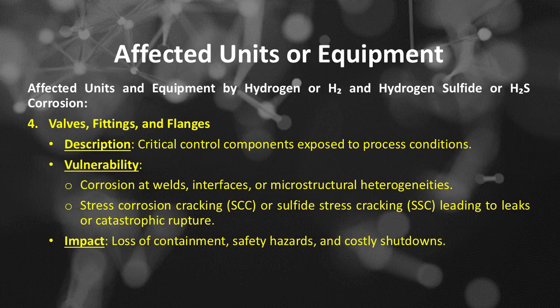The vulnerability of high-temperature hydrogen or H2 and hydrogen sulfide or H2S corrosion to the valves, fittings, and flanges includes localized attack at sealing surfaces, threads, and joints, pitting and crevice corrosion under gasket or bolted assemblies, embrittlement and cracking under high-stress and corrosive environment. The impact of high-temperature hydrogen or H2 and hydrogen sulfide or H2S corrosion to the valves, fittings and flanges: leakage, operational failures, and maintenance challenges.